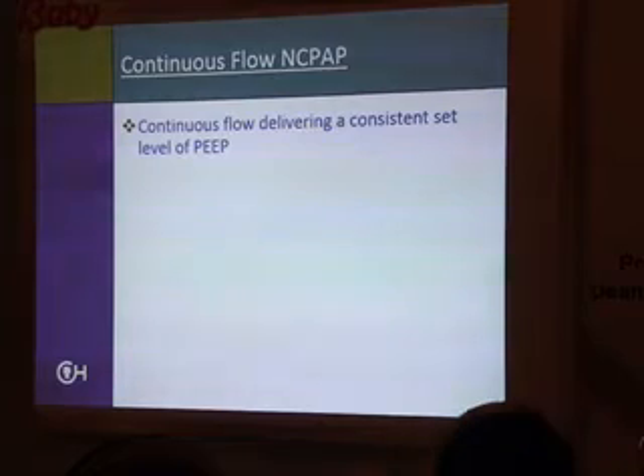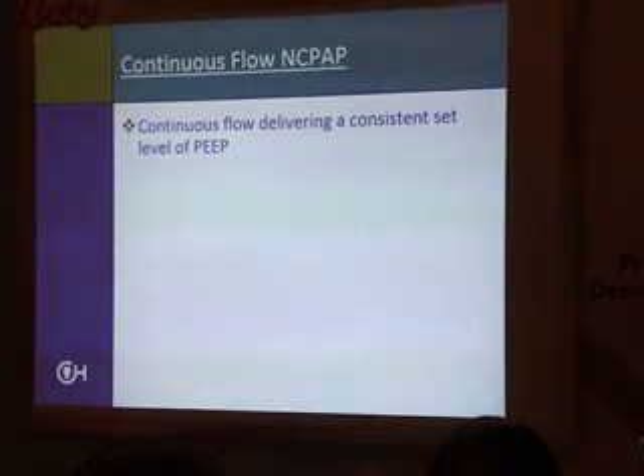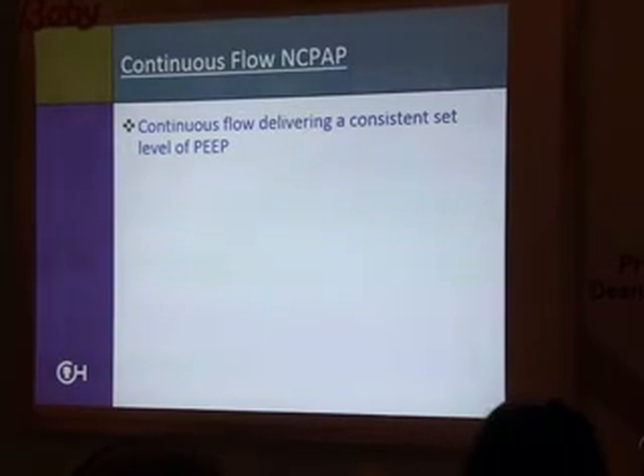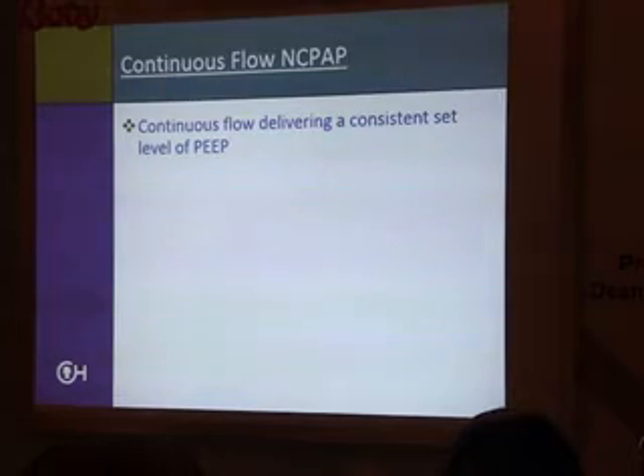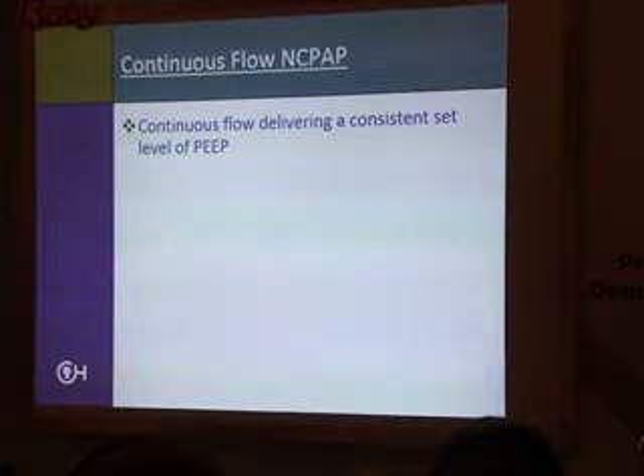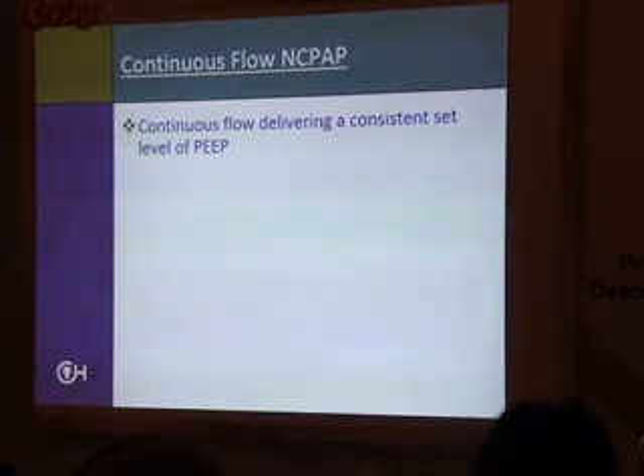So starting with continuous flow CPAP, this is when a continuous flow is delivered through the ventilator to achieve a constant level of PEEP. Depending on your leak, that flow might change a little bit, but for the whole phase of your breath, inspiratory and expiratory, you have the exact same flow level that's going through the circuit. Most commonly, this is delivered through a ventilator, so through the Dragers or whatever type of ventilator you have, the Aveas, the Servos. If you're in CPAP mode for any of those, this is a continuous flow mode of ventilation.